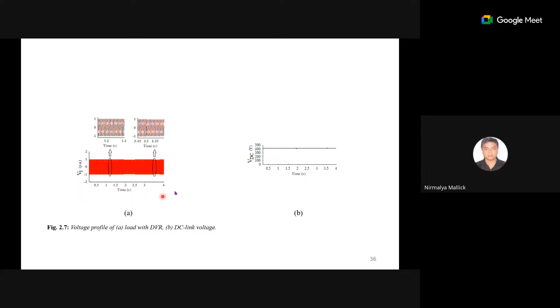At the instant when this is going on, the DVR is ready to supply the required amount of voltage. This is the voltage supplied to compensate the dip caused by motor starting, whereas this portion is due to the steady symmetrical fault. This is the load voltage, which is almost regulated, and this is the regulated DC voltage.